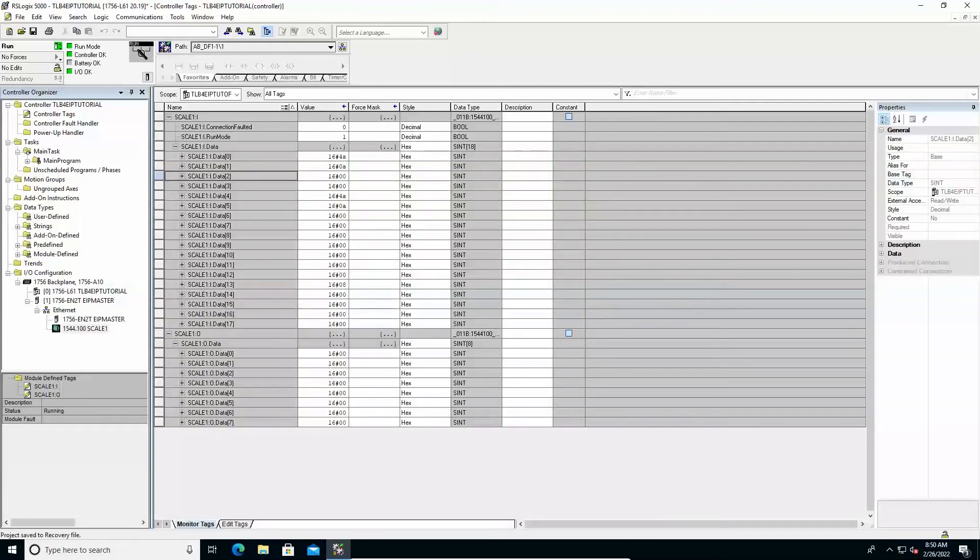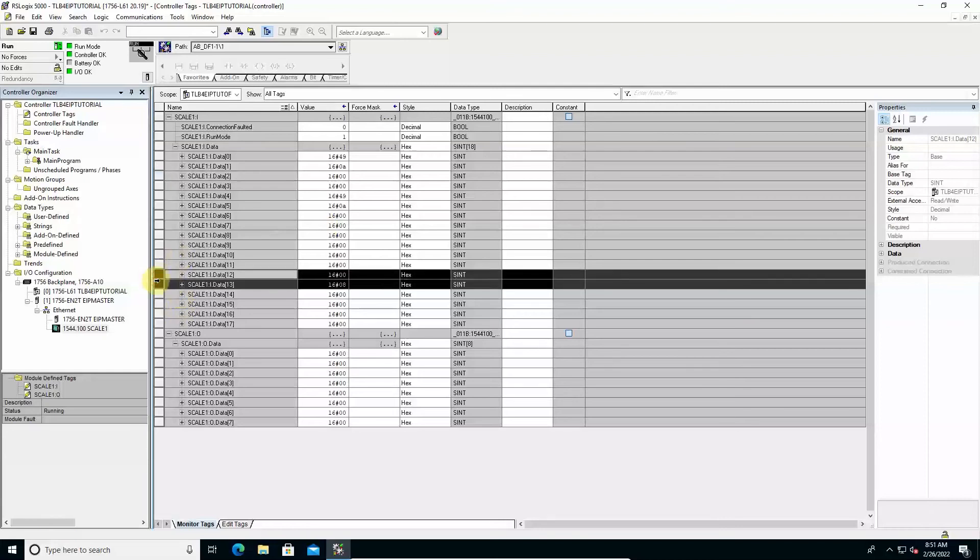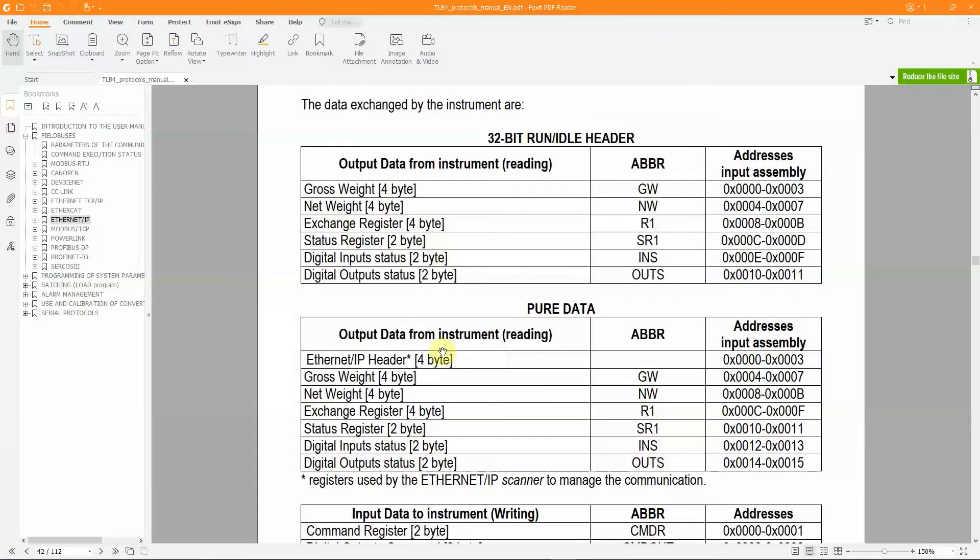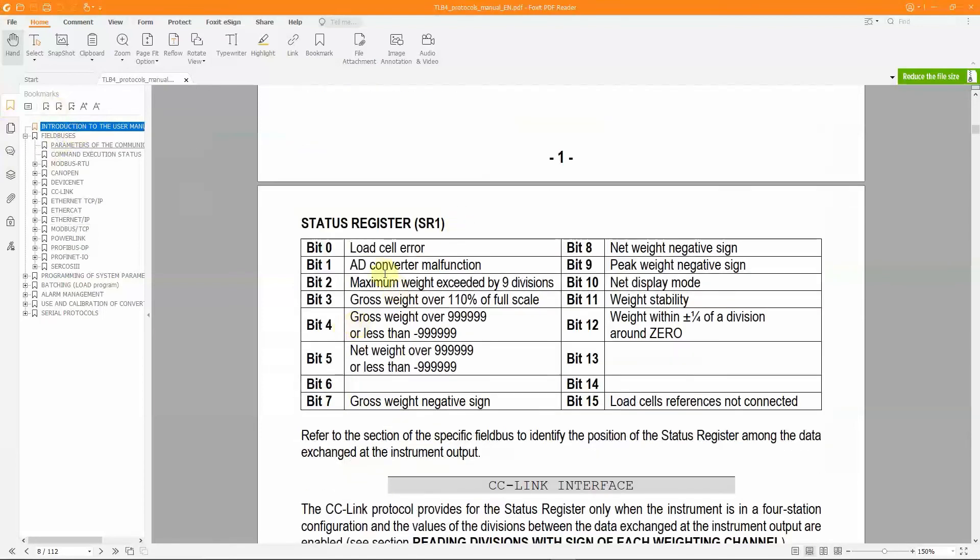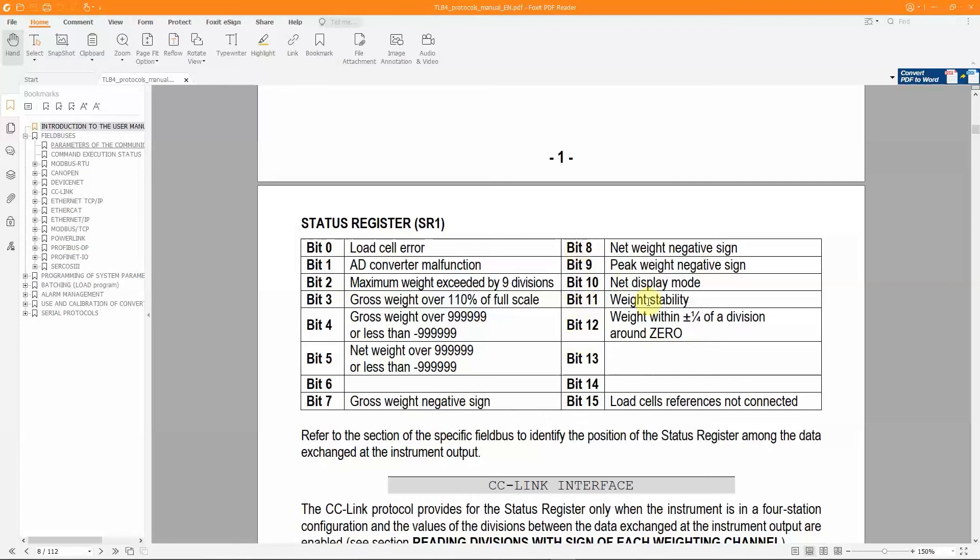The information about the sign of the weight values is available, in addition to other information regarding the operating status of the instrument, in the bits of the status register. In the protocol's manual, a specific table shows the meaning assigned to each of the 16 bits that make up this field. Particularly, bits 7 and 8 indicate the sign of gross and net weight, equal to 1 when the corresponding current weight is negative. Bit 11 is equal to 1 if the current gross weight is stable, otherwise it shows 0.